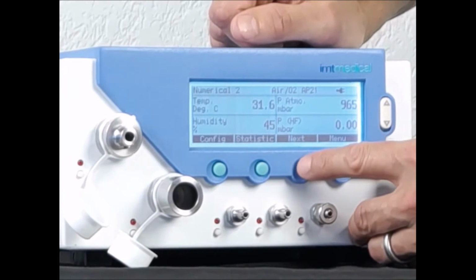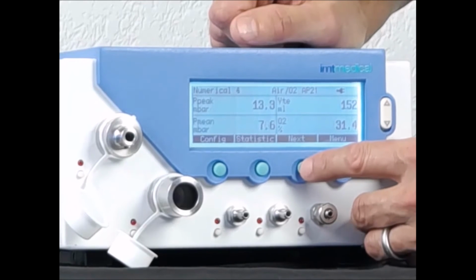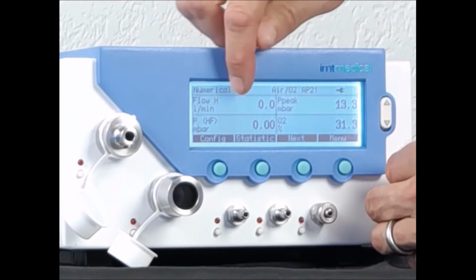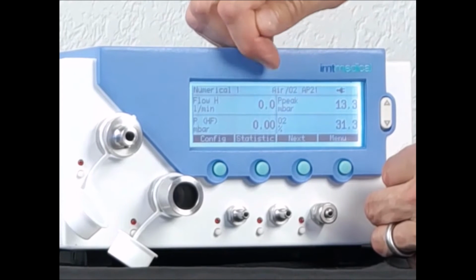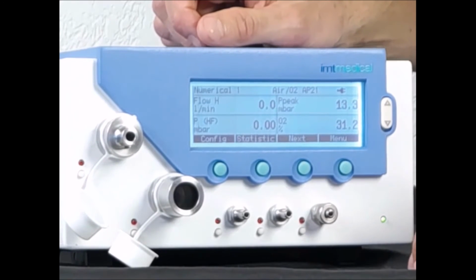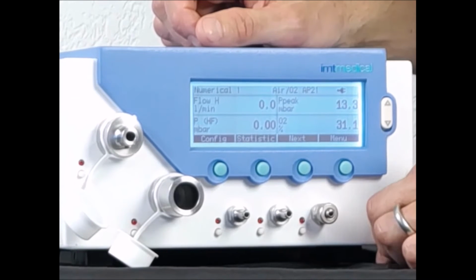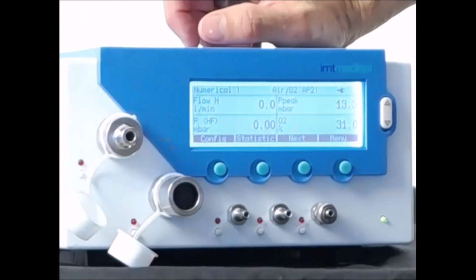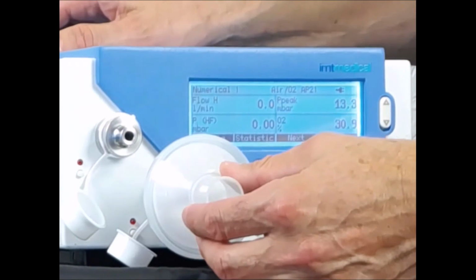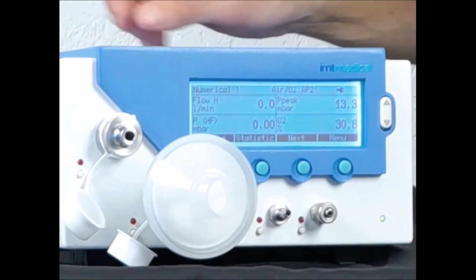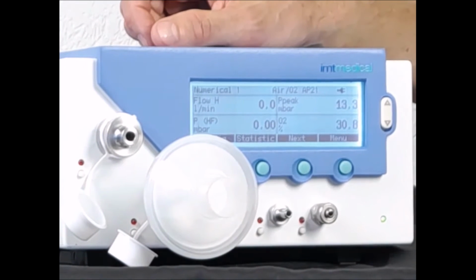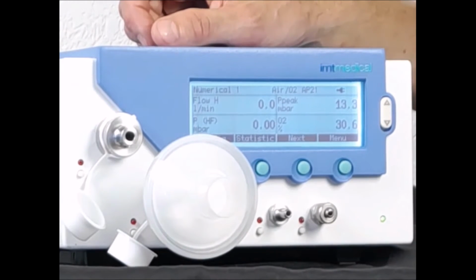We can very nicely see that on my flow here. Flow is zero, pressure is zero, so these two values need to be exactly zero. Then my offset is corrected correctly. Of course, we need to attach the filter. And now I will show you how to perform an oxygen calibration. Again, oxygen calibration is enough every week or ahead of very important oxygen measurements.